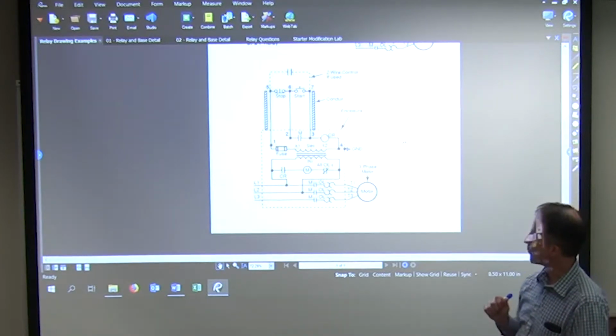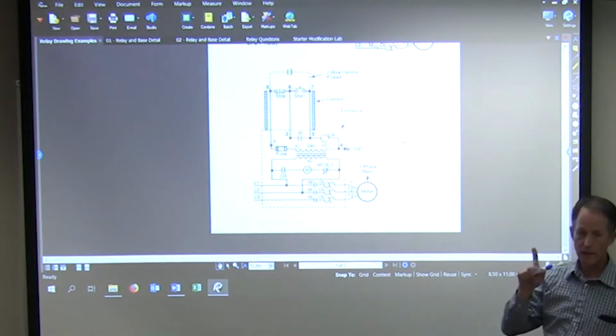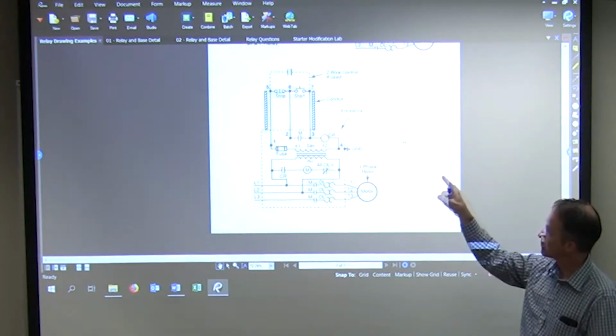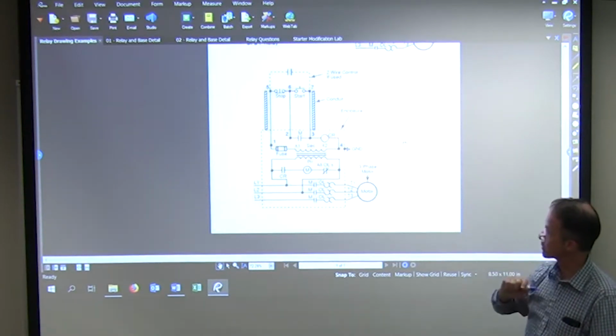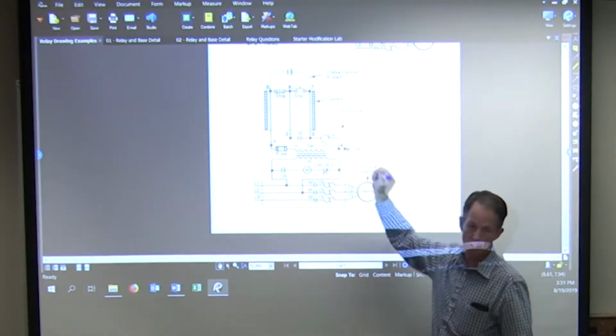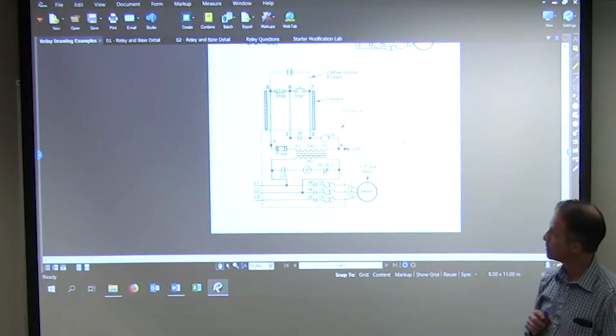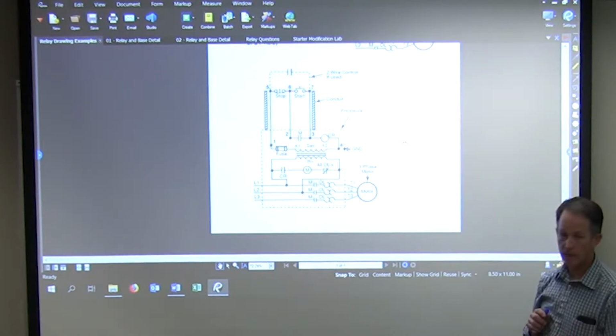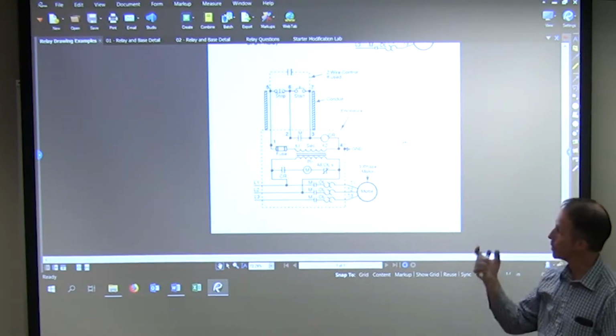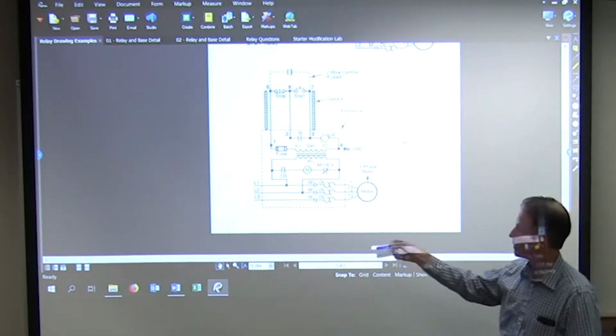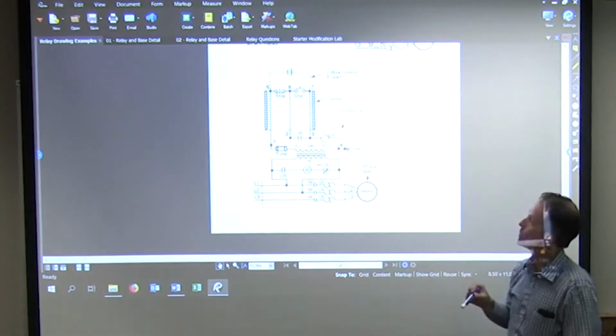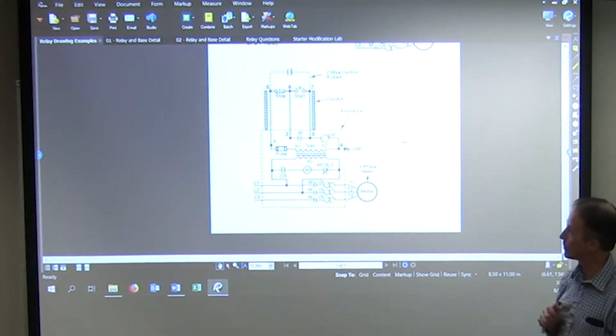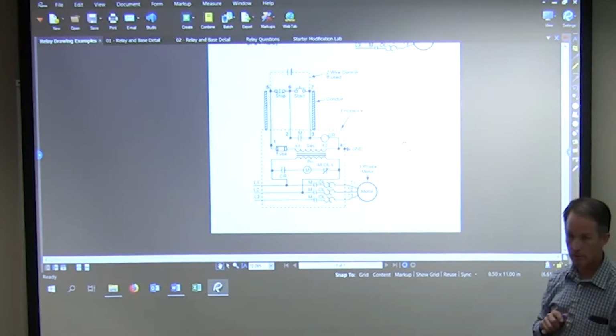Okay, so right now before I start it, what's my voltage at 6 compared to 4? Say we're 120 volts on our secondary. It'd be the full secondary. So I'd have 120 volts at 6, right? So full voltage there, just waiting. I'd also have 120 volts at 2, waiting for that one. So I press the start, then what happens? CR pulls in.